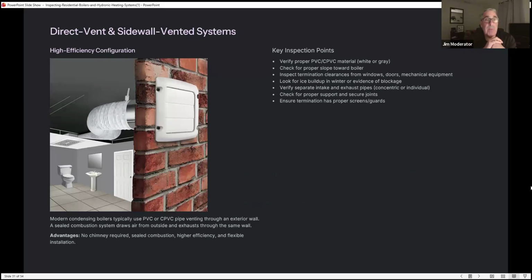Direct vent and sidewall venting systems. For high efficiency configuration, the modern condensing boilers typically use PVC or CPVC vent piping through an exterior wall. A sealed combustion system draws air from the outside and exhausts through the same wall. Advantages: no chimney required, sealed combustion, higher efficiency, and flexible installation. So the key inspection points would be to verify proper PVC and CPVC material, which is white or gray.